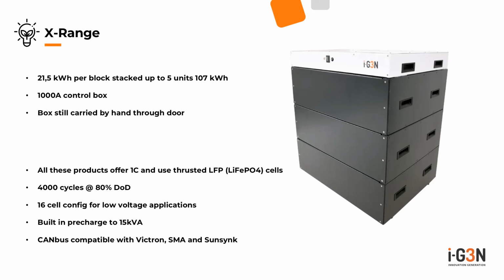All of the products covered so far offer a 1C output and are based on trusted lithium iron phosphate technology. As i-G3N, we only bring in first-tier manufacturer cells, so only EVE and CATL cells, all rated for 4,000 cycles at 80% depth of discharge. We only do 16 cell configurations, giving a good voltage range for low voltage applications. All of these products have a built-in pre-charge that can handle a 15 kVA Quattro or similarly sized system. They're CAN bus compatible with Victron, SMA, and Sunsynk, which is our main form of communication for those products.